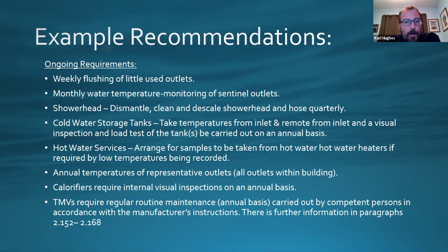Monthly temperature checks on the sentinel outlets. Now, the sentinel outlets are the nearest and furthest. So whether that's the nearest to the incoming main or the furthest away from the incoming main, and the same with the cold water storage tank, same with the hot water cylinder, the nearest and furthest, etc. Shower heads, because obviously these are a risk as they're creating an aerosol. You need to make sure that they're dismantled, cleaned and descaled on a quarterly basis. Cold water storage tanks, you take a temperature from the inlet and remote from the inlet, on an annual basis. So what they usually say now is in the summer months, where that tank temperature could be at its worst, that's when you would do your inspection and your temperature checks there.